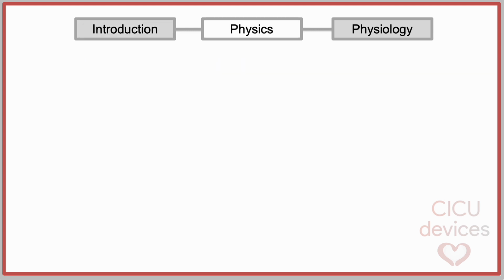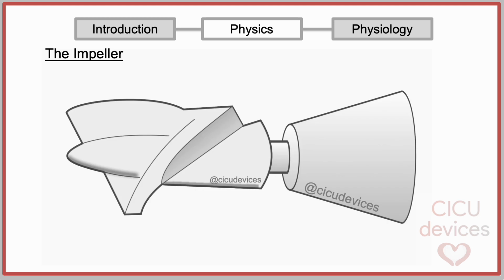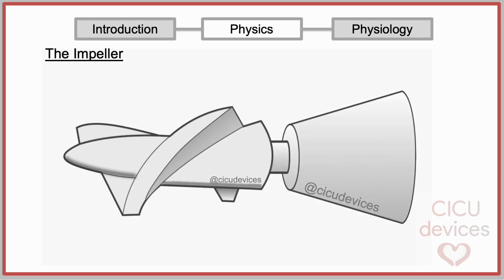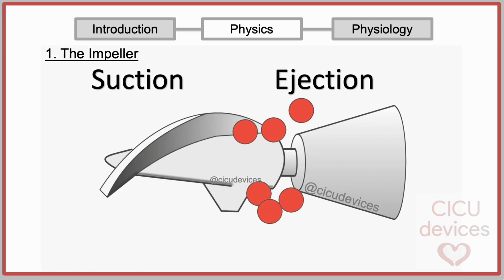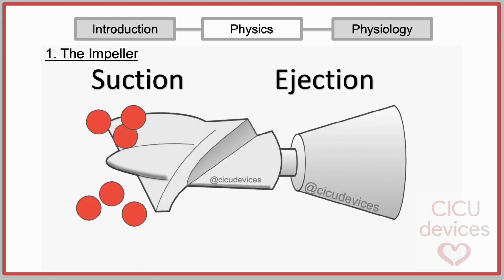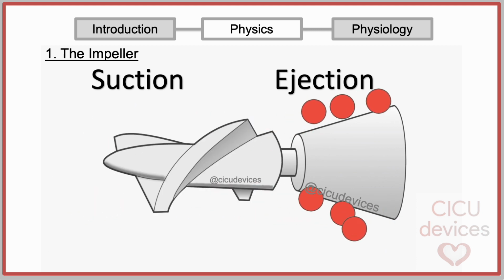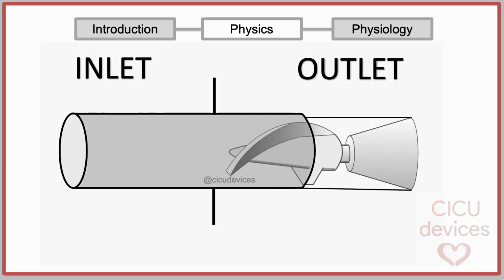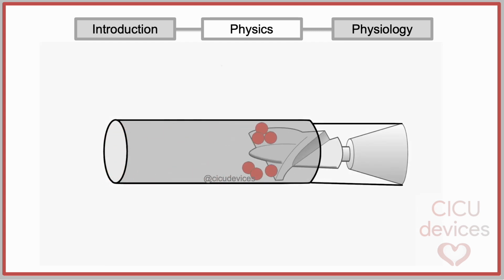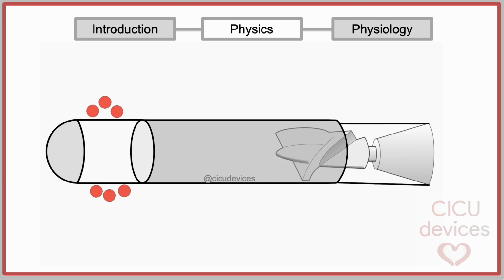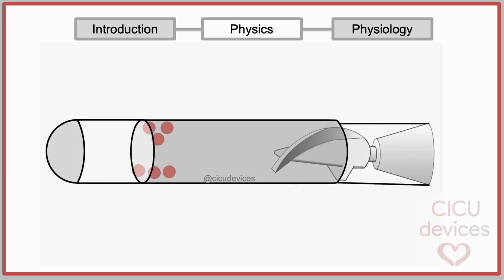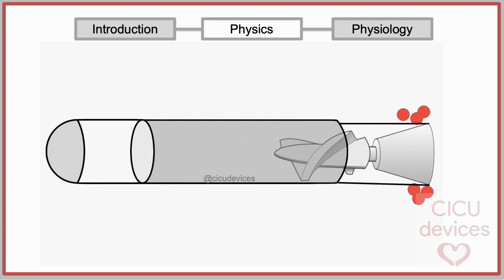Next, we are going to review the physical principles that explain the operation of the Impella catheter. The Impella pump is a miniaturized axial pump. It operates in continuous rotation, where the blades generate suction at one end and positive pressure at the other end. So, if we add a tube, we can transmit the suction to the inlet and ejection to the outlet. This way, the flow will follow the generated pressure gradient. Finally, we would only need to add a grid at the inlet and a blunt tip, both to prevent damaging cardiac structures. We would then have a very basic Impella.